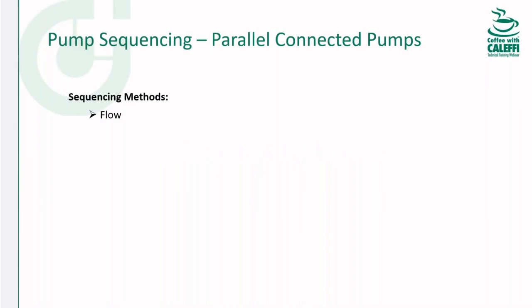So there are several methods. Flow-based sequencing is pretty much outdated, so we're not really going to discuss it. Speed-based uses predetermined pump speeds. So for example, when pump one is running and it gets above 96% speed, just stage on pump two. And so there are stage on speeds and then there are stage off speeds.